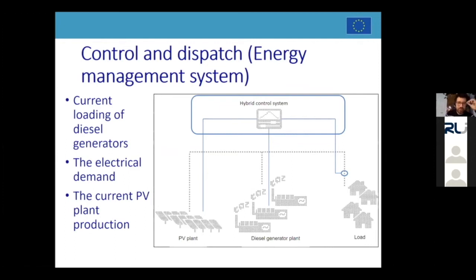Then we also have control and dispatch systems. Once you go beyond a simple or a diesel-only system, you need to make sure that, for example, the PV plant is communicating with the diesel generator plant, because in case of a quickly ramping up of the PV power, the diesel needs to be reduced or switched off, or the PV needs to be curtailed to not cause any damage to the conventional power plant.